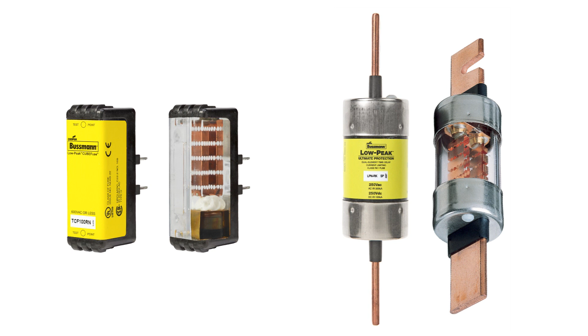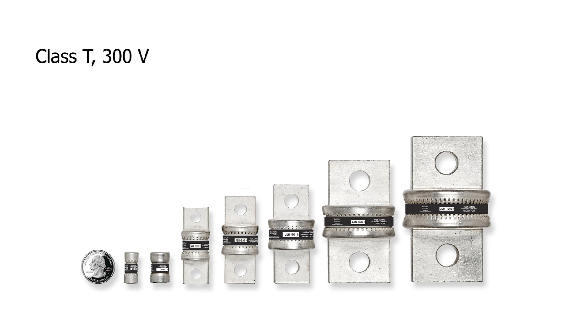By operating on thermal energy principles of physics, the fuse improves electrical system reliability by not relying on springs, levers, or latches that require periodic maintenance to ensure continued proper operation. Fuses are factory calibrated devices that do not require any adjustments or settings in the field. This minimizes possible misapplication of the device, and engineers can be certain the level of protection specified is met and retained.